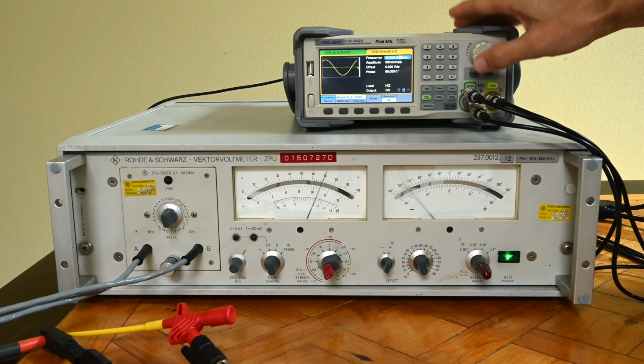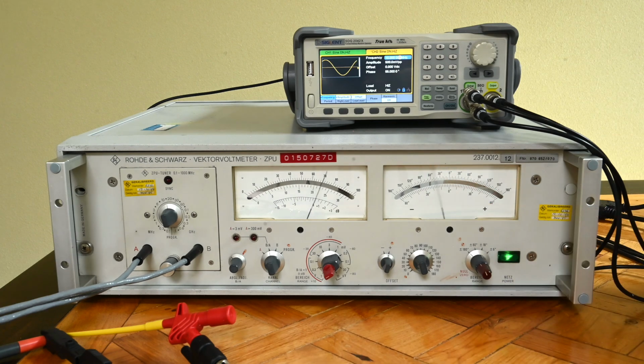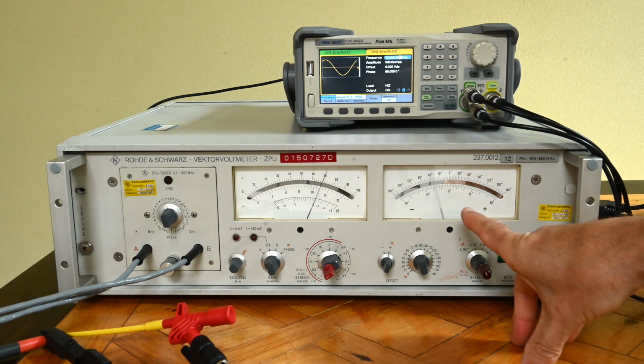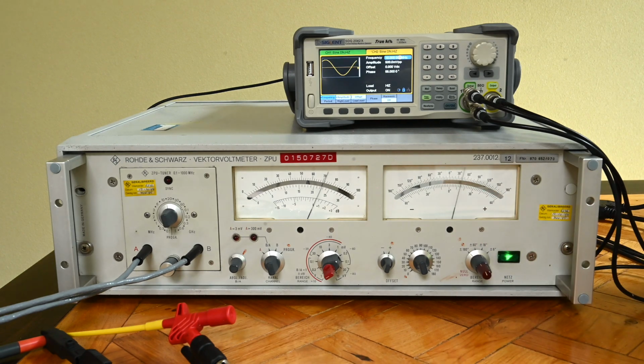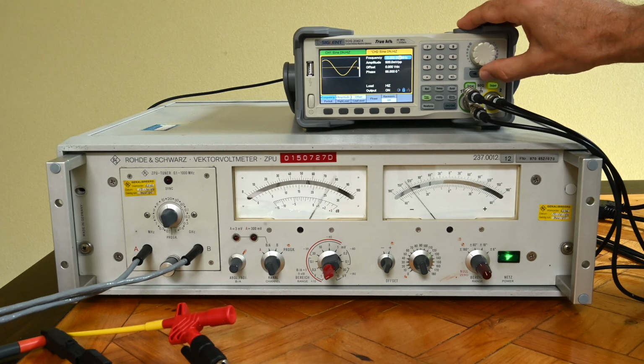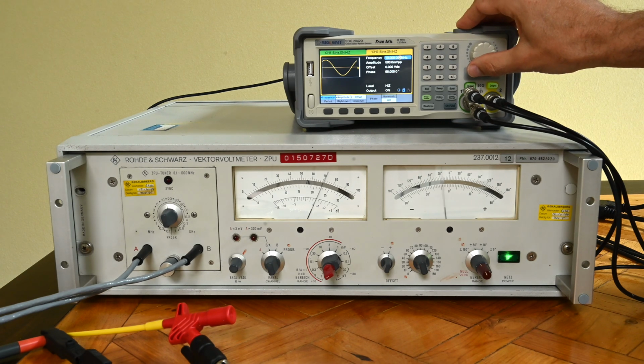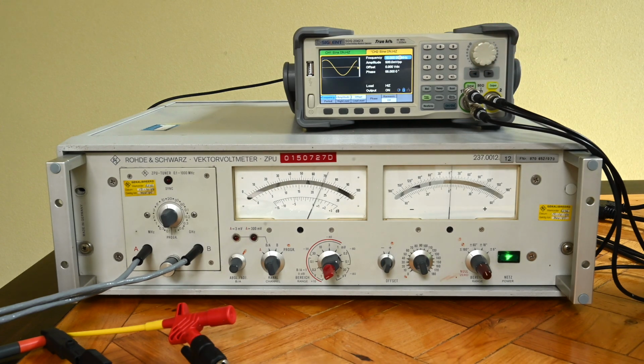And what happens here? Every second we see the meter going to the extremes, more or less. This is exactly what we should expect to see, because it's one hertz off, so every second it goes through that cycle, and if we go faster, then it would go twice a second or so, making this type of movement. So this really allows us to calibrate or test two sources to see that they have exactly the same frequency.